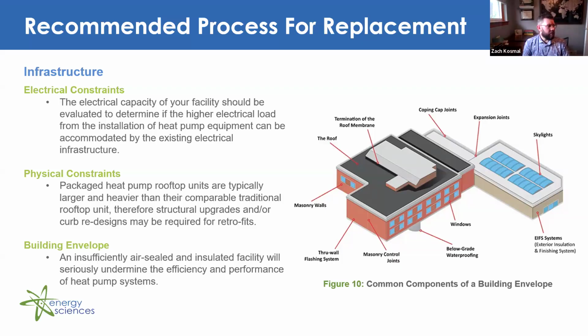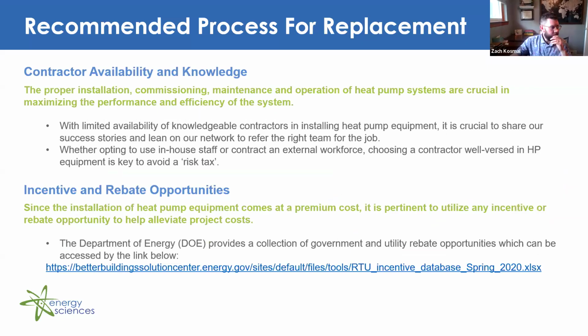And as previously mentioned, packaged heat pump rooftop units are typically a little larger and heavier than your traditional rooftop unit. So you may have to make some structural upgrades, such as curb redesigns or retrofits. And then, as mentioned previously, building envelope. An insufficiently sealed and insulated facility will seriously undermine the efficiency and performance of heat pump systems.